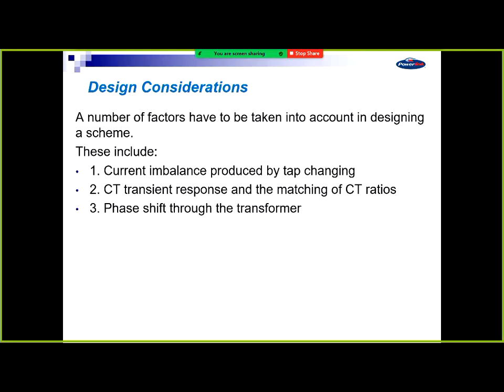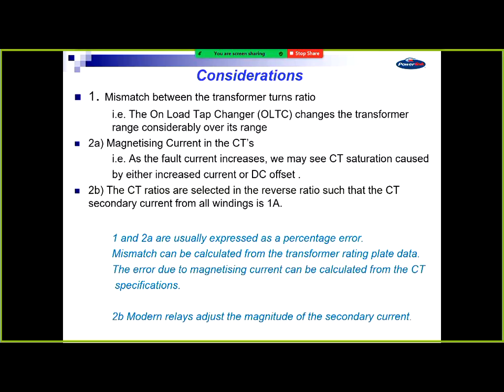Phase shifting is also a concern. Dealing with zero sequence currents is another issue you've got. A star transformer that's got the neutral earthed is a zero sequence source. So, depending on which side it's on, one of the external CTs won't have that zero sequence current flowing in it. If you don't take that into account, you can trip because it's a zero sequence source. Your inrush current is another concern. So there's the mismatch between transformer turns and the on-load tap changer, the magnetising current in the CTs, and the CT ratios.